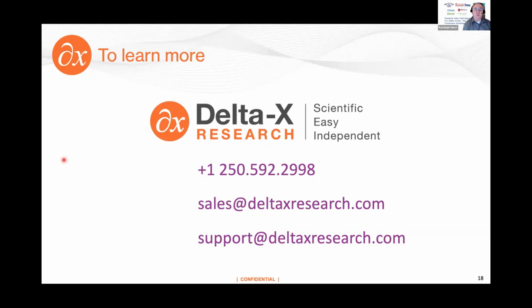Is it true a large number of online DGA monitors are not connected to the transformers? Not connected to the transformers? Yeah. Well, I have heard of some utilities buying them and having them in the warehouse and not installing them. That has occurred. I think more often than not these days, though, on new transformers, utilities are speccing them in, so they're being installed at the factory. The issue is the communications more often.